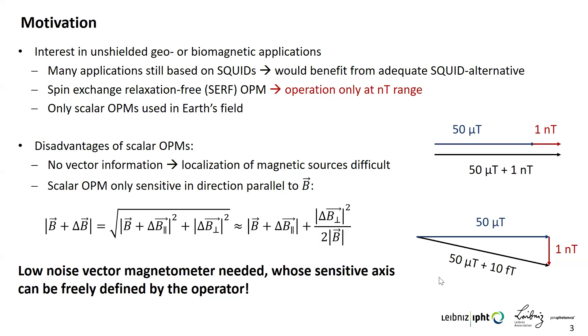Scalar OPMs are only sensitive in the direction parallel to the background field. If we operate in Earth's magnetic field of about 50 microtesla and want to measure an anomaly of one nanotesla: if the two vectors are aligned, the scalar value changes by exactly one nanotesla. But if they are perpendicular, I measure only a change of 10 femtoteslas, suppressed by the background field via a Pythagoras-like equation.